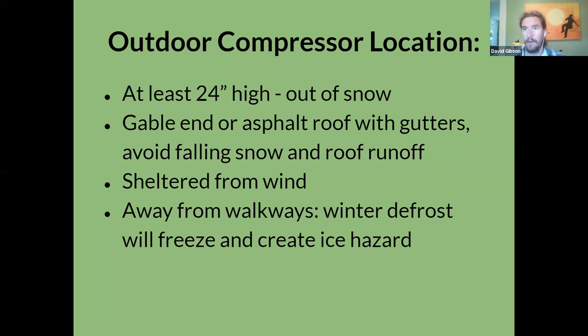And so it needs to be up off the ground so that water can run somewhere. And then my final note on here is you don't want it right next to a walkway, because that water will refreeze and can create a slipping hazard. And so you generally don't want it right next to a walkway where you'll cause ice problems. I recommend putting the outdoor unit on a gable end, or if you have an asphalt roof with gutters where there's not going to be snow sliding off the roof or constant water running off the roof.